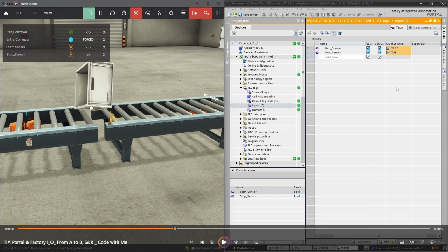It's called a normally closed and normally open sensor. It's easier in our head, actually, if something is in the sensor's path, it should be true. If you want to think like that to make it easier logically, you can invert the signal when you're actually going to use it. I will do this in this video, and I always do it just to make programs easier to write. I will show you how to do that when we come to that piece in the video.